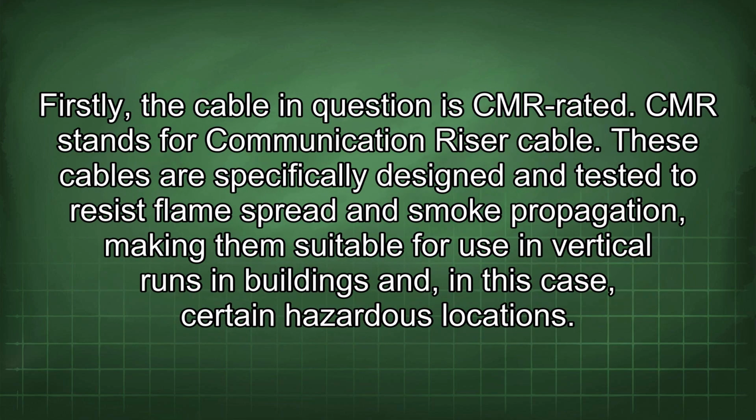Firstly, the cable in question is CMR rated. CMR stands for Communication Riser Cable. These cables are specifically designed and tested to resist flame spread and smoke propagation, making them suitable for use in vertical runs in buildings and, in this case, certain hazardous locations.